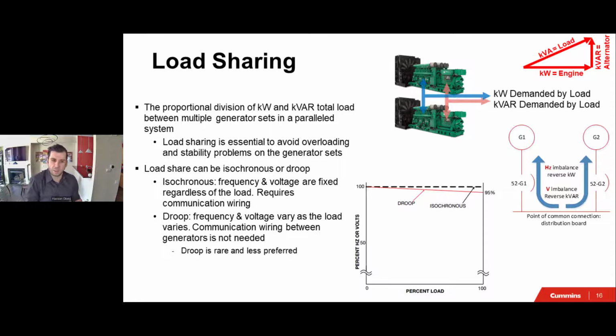Once I describe this to you, you're probably thinking, okay, I want to stick with isochronous, and this is the preferred way, and this is what we see the specs asking for. Isochronous is the more advanced mechanism to do load sharing. However, it requires communication between the generators. We have to run cables, one cable with 4 conductors inside of it, shielded, 2 for the VARs and 2 for the kW.